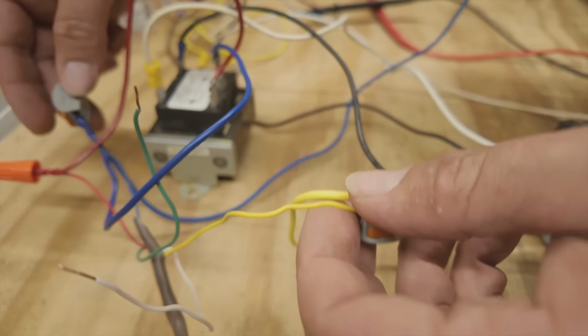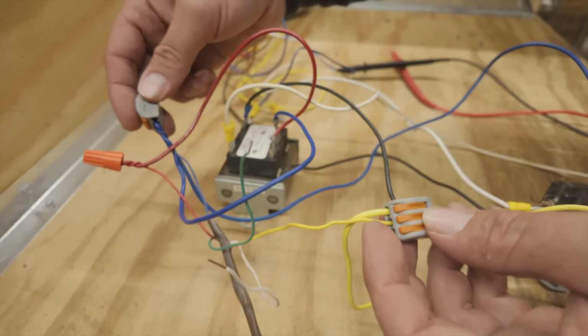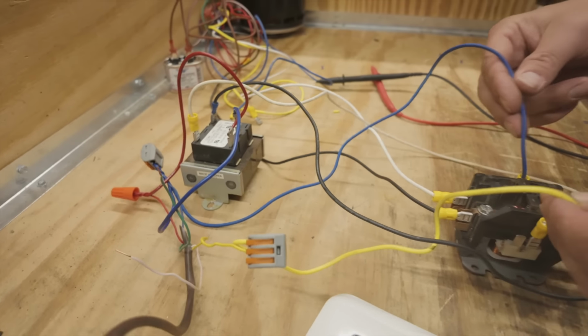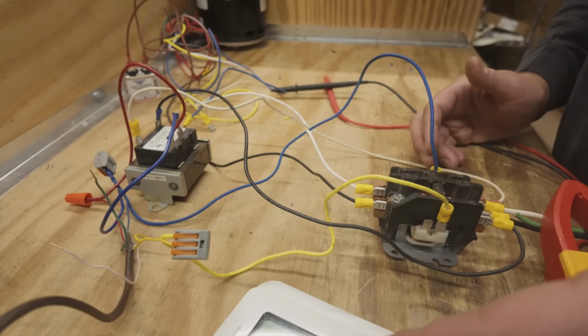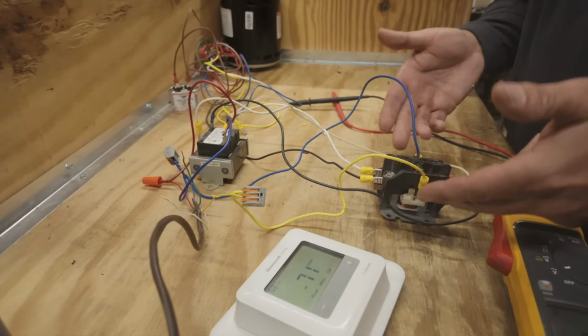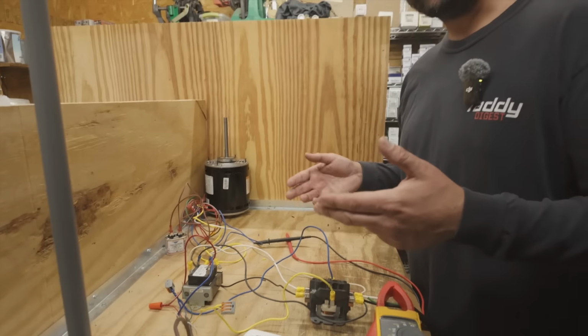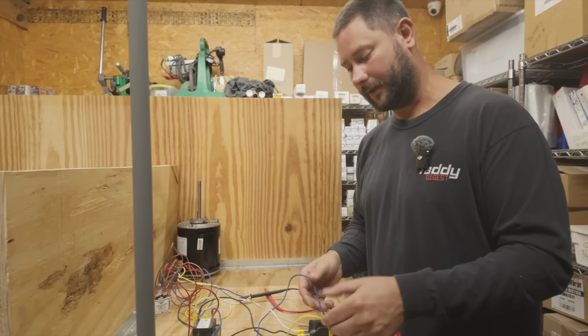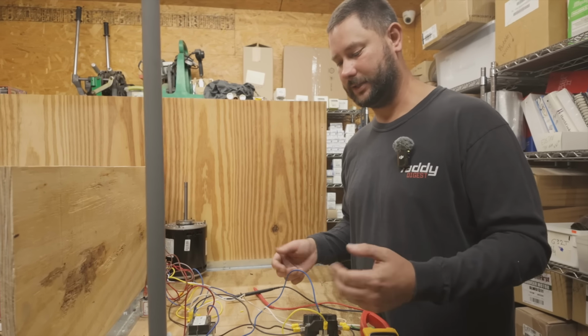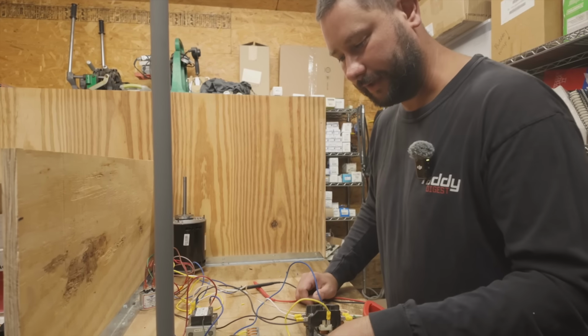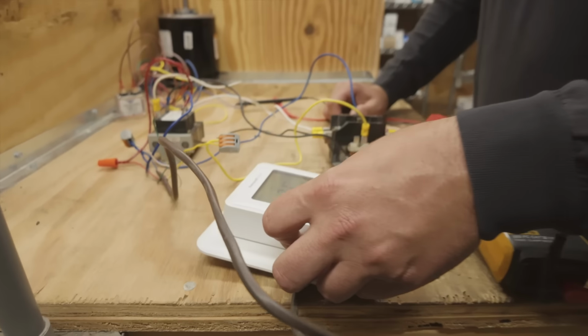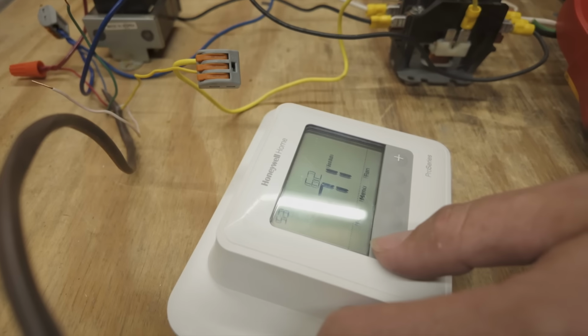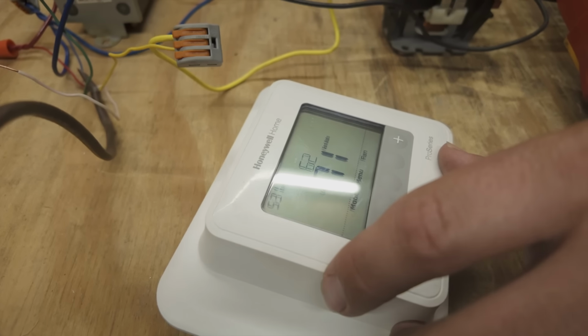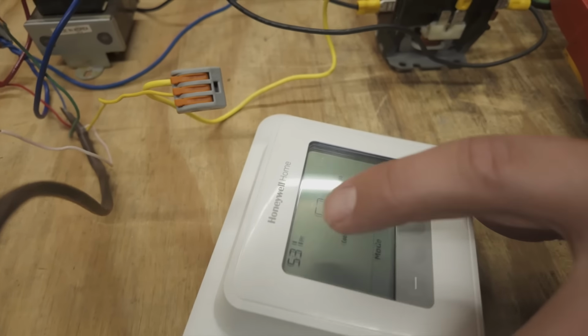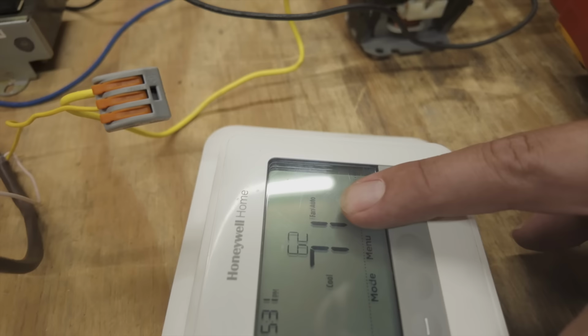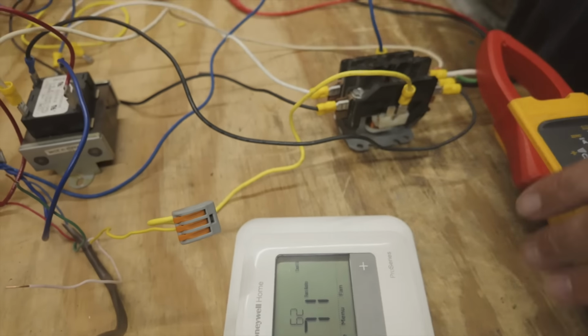So between C and Y, we need a call, right? Whenever we give the thermostat a call, it provides 24 volts to that yellow wire. And then that will give 24 volts to the coil of our contactor. So we're going to do that real quick. I'm going to push mode until it says cooling. And then it should say cool. And that's going to send 24 volts.